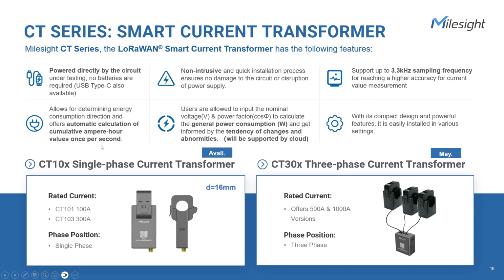One thing worth mentioning is that the CT sensors are specifically designed for detecting AC circuits and are not compatible with DC circuits. The majority of project requirements we receive focus on the precise collection of RMS (root mean square) voltage and current data to enhance power system monitoring. The CT series is perfectly suited to fulfill these demands. It supports targeted detection of high current loads in a wide range of applications, including refrigeration systems, construction sites, industrial HVAC systems, and monitoring of small electrical appliances in buildings.